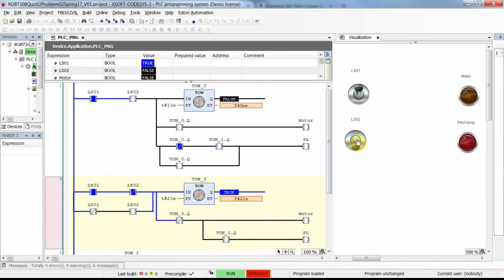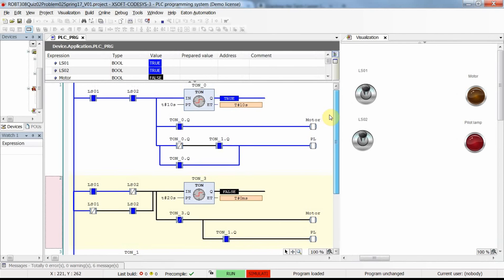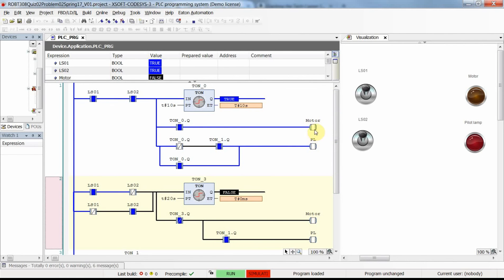Now let's check when both inputs are true. I turn both on and the timer is activated. During these 10 seconds we expected the pilot lamp to flash and the motor to be off; after 10 seconds the motor should turn on. These contacts are true, so the motor should turn on — but it's not. Something to keep in mind: we have the motor coil in two rungs. The program executes top to bottom, so in the first rung motor is set true, but when the second rung executes without logic continuity, motor turns off.